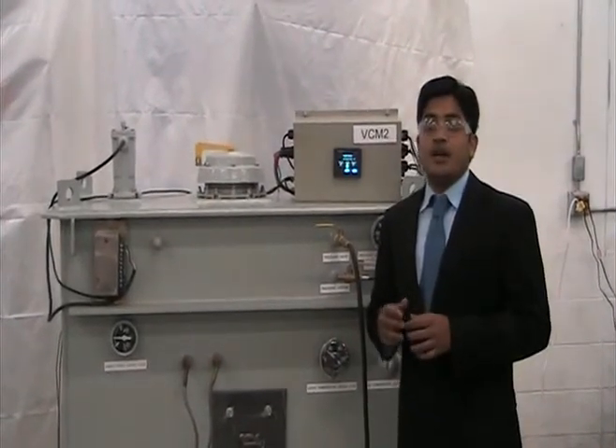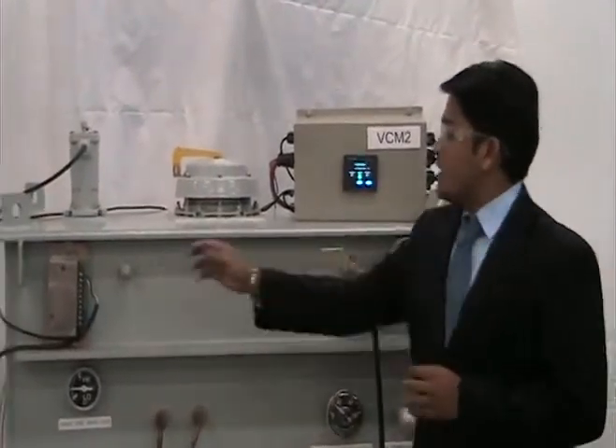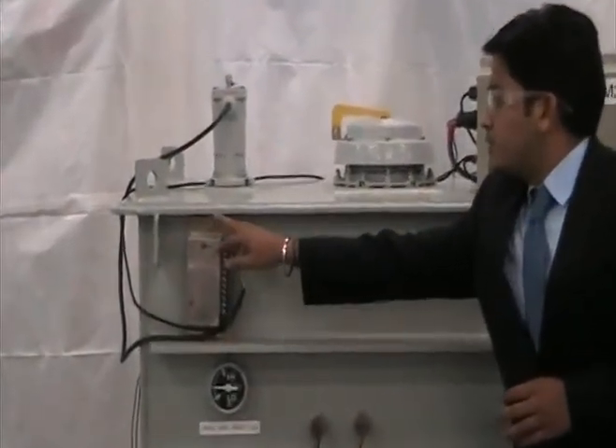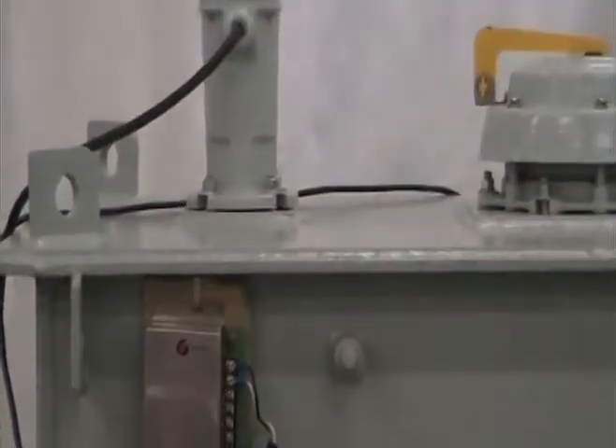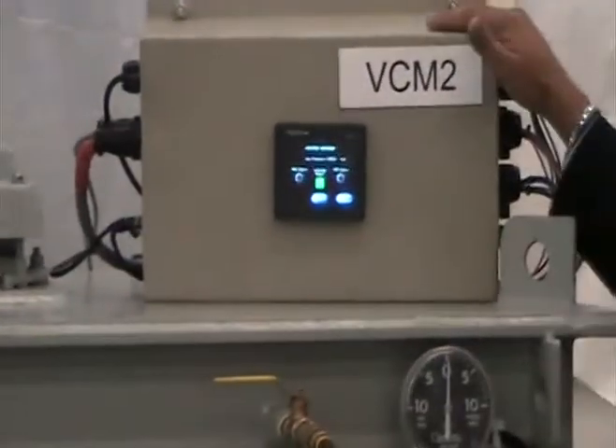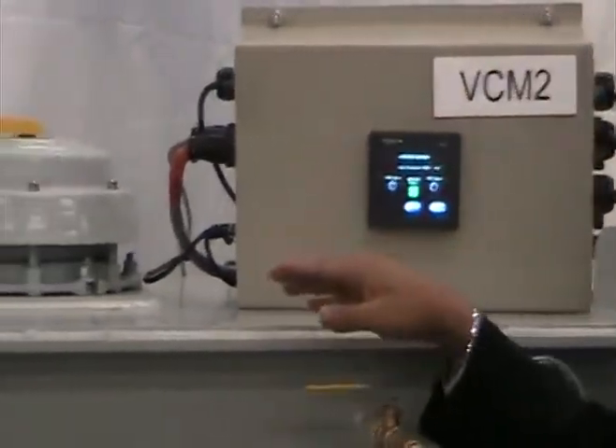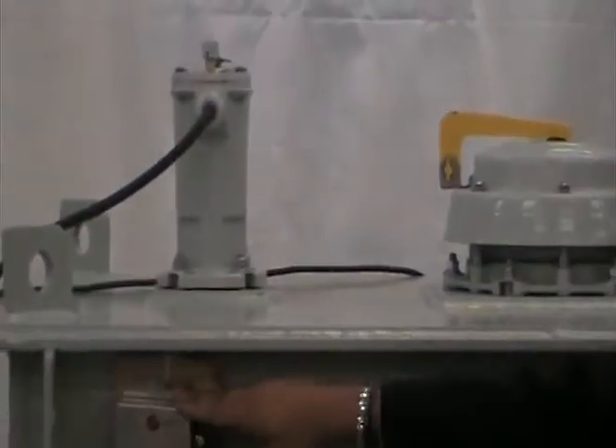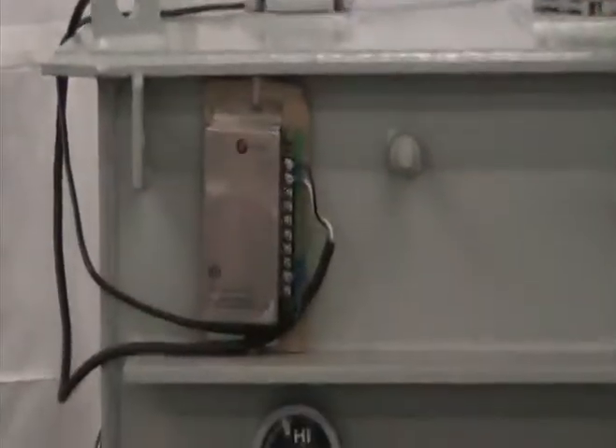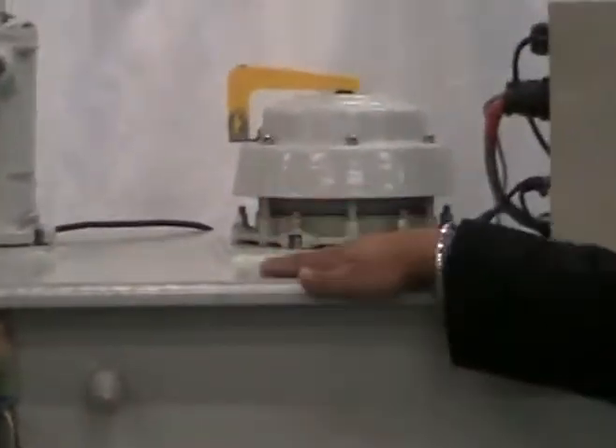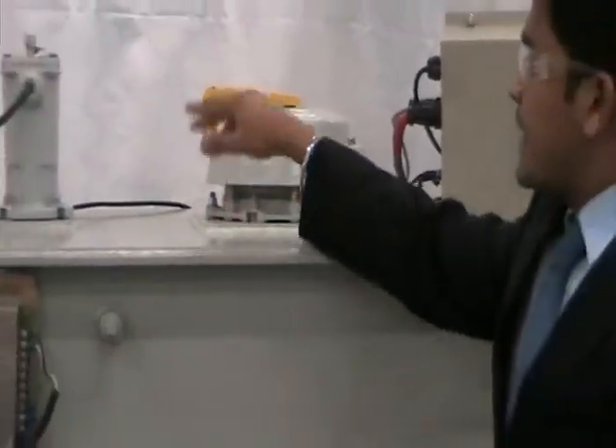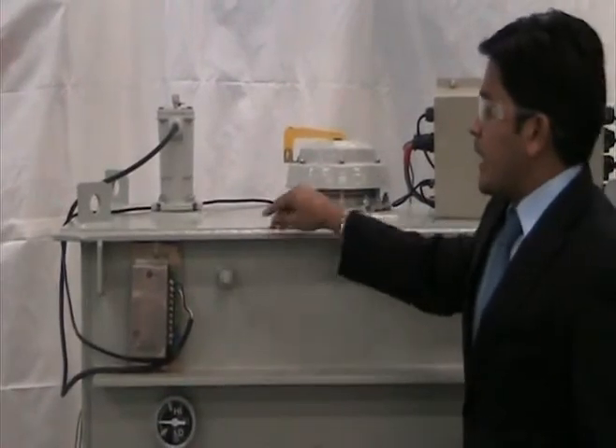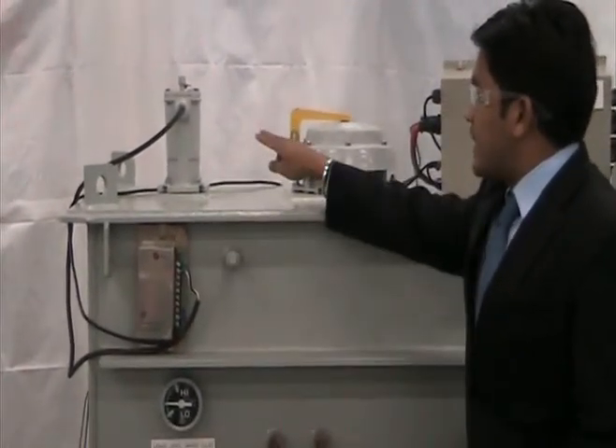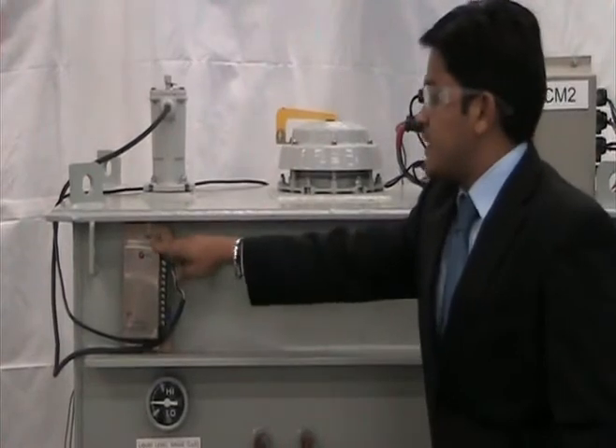Now I will demonstrate how VCM2 can detect the sudden change in the pressure. We have used a sealing relay to compare the VCM2 results. VCM2 uses a sensor to detect the sudden change in the pressure. The conventional method uses sudden pressure relay and sealing relay. When the pressure inside the transformer goes more than 2 psi per second, the SPR will be activated and the sealing relay will detect the SPR activation and it latches the signal.